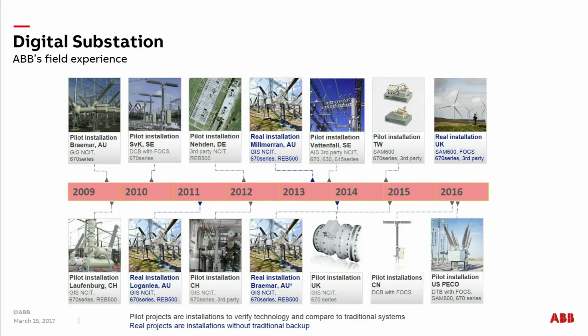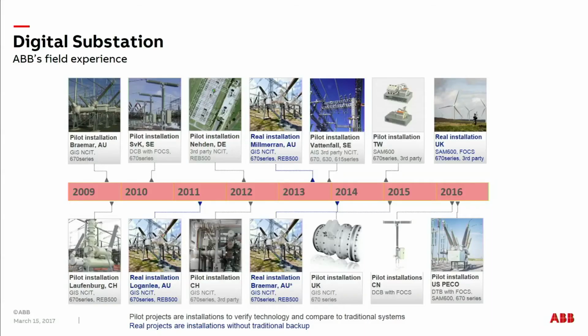That would have been my next slide. Of course, we do not talk about things which do not really exist. We have more than 300 high voltage sensors for current and voltage measurement installed worldwide. The biggest bulk is in Australia. We have 5 substations which have been working since before 2000. We have tested it for more than 10 years, and since 2010 they are in operation with the process bus standard I was talking about. So we have more than 10 years of experience. I think we are the company with the longest experience - we have basically been thought leaders in this development.